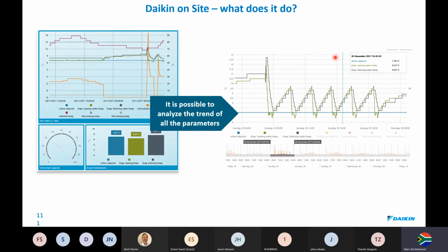So here you can pretty much see you have a dashboard. You can remotely go on and see your chillers running at say 30%. You can see what your set points are. If you're owner of a factory, for example, you can see what your process is doing, what important temperatures are running. If your machines are getting too hot, you melt plastics, the molds jam up and freeze. It's downtime. It's a waste of cost of raw materials. So all of this can be monitored off this very easy to read dashboard.